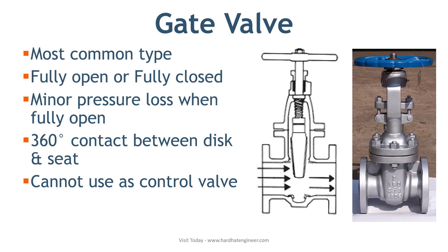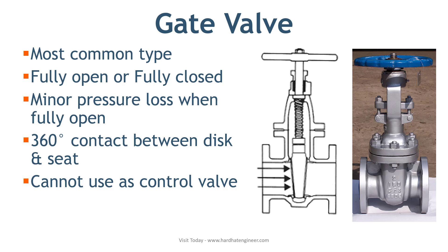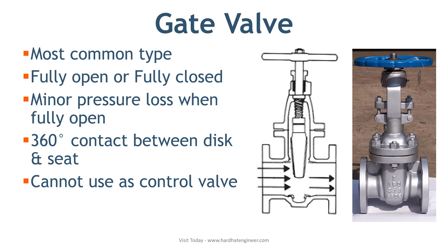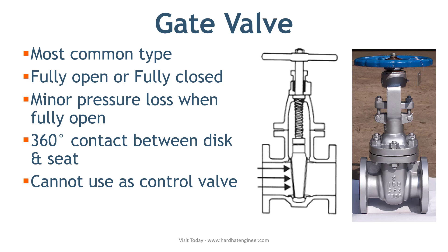Gate valves are used to start or stop the flow of liquids, but not for regulating the flow. The flow path in a gate valve gets bigger when you start opening the valve. A partially opened gate valve creates a lot of noise and vibration. Near shutoff, high fluid velocity causes the disk and seat to erode, and this will lead to leakage over a period of time. So in operation, gate valves are either fully open or fully closed.